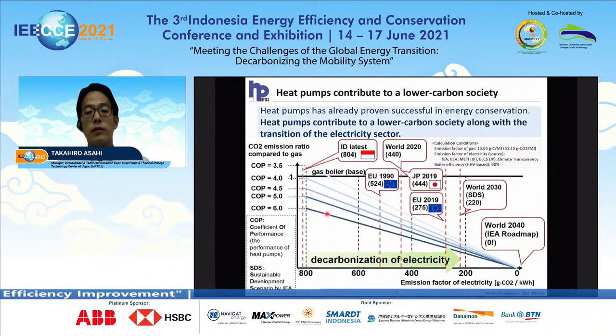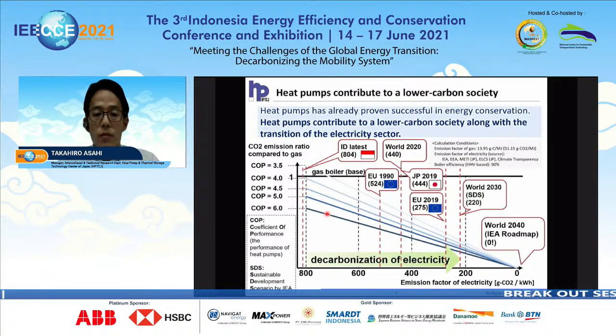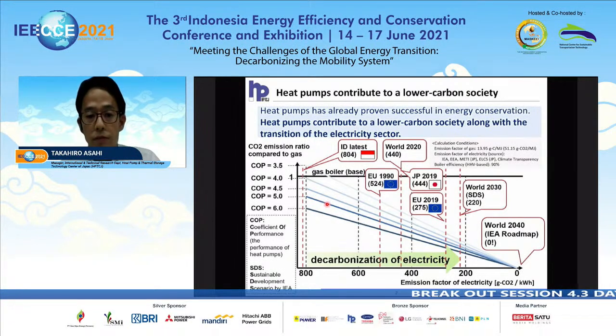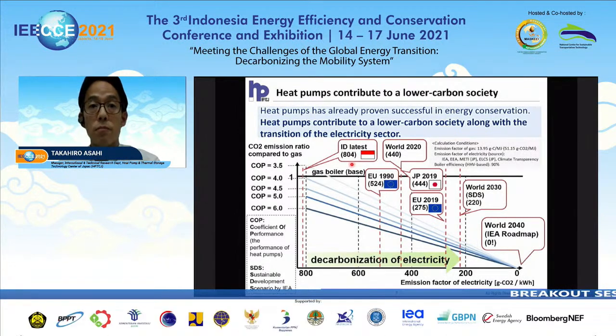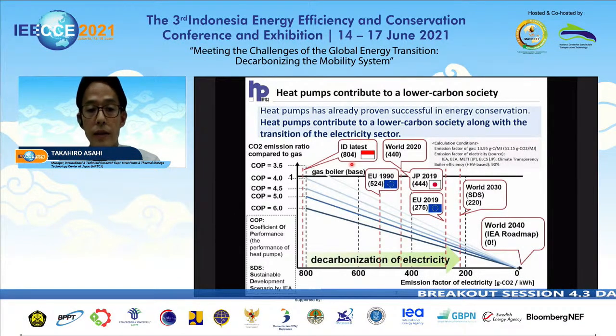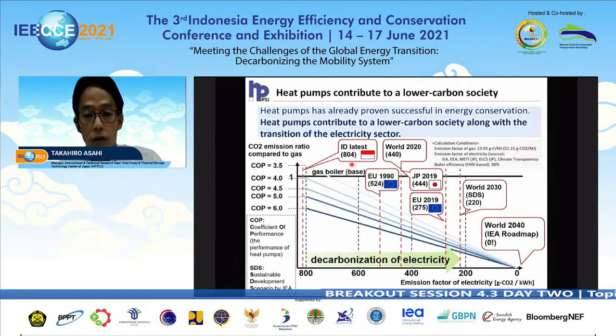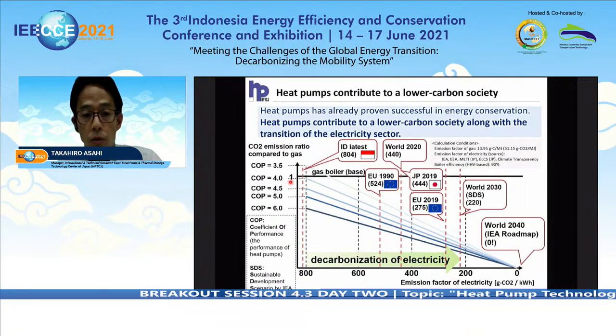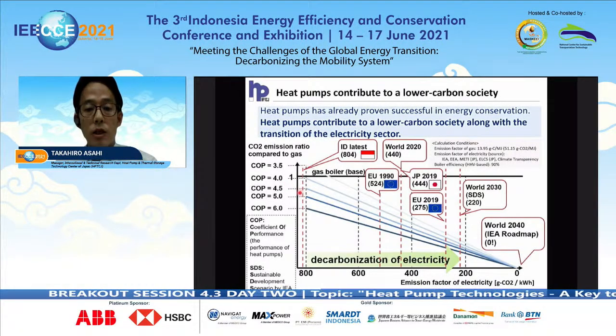I assume a boiler efficiency of 90% in this chart. I put emission factors of different countries and years on this chart. Indonesia's average is around 800, though I know it's different from province to province. In this case, a COP of 4 is required to be lower carbon compared to gas boilers. The higher the COP, the less CO2. This is the situation as of today.